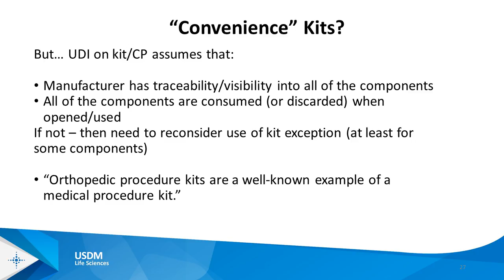So again, it's important to document and understand each of the exceptions, and there's discussion and criteria of them both in the rule and the preamble, and understand that as you move forward and if you decide to take advantage of any of the exceptions that are integral to the rule. In the same way, there is an additional requirement for direct marking. So in addition to the label requirement that we've already talked about, for those devices that are intended to be reused and reprocessed between patient use, there needs to be a UDI on the device itself.